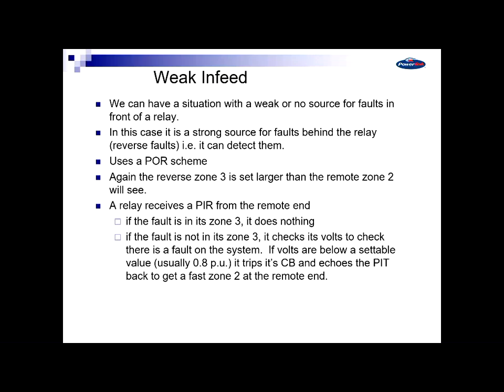There can be parts of the network which are not weak in feed, but we take a feeder out of service or the generator's offline for maintenance or something, and it becomes a weak in feed. If that's the case, we just turn on the weak in feed. If you see the fault in front of you, you still send a signal to me. So if you do see it in zone 2, you still send a signal to me. They're always used with permissive overreaching schemes. So if you see it in front of you, you send a signal to me and tell me to trip. If you see it in your zone 2 and I send you a signal, you trip.